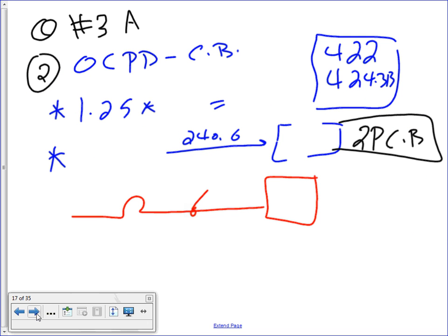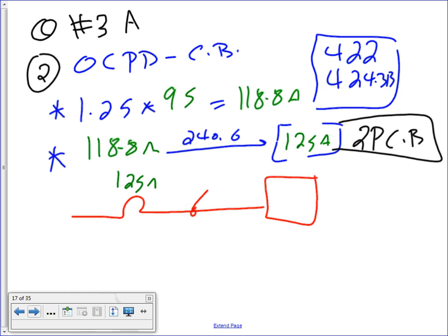Overcurrent protection device. We're assuming, guys, it's a continuous load. It's an appliance, but it's a heating appliance, so they allow you to use 95. So you take the 95 multiplied by 1.25. That will get you the same thing, 118.8 amps. Your reference is 422.11, 424.3(B), which tells you to multiply by 1.25. You take the 118.8 amps, 240.6, that will get you a 125 amp 2-pole circuit breaker. Then you put yourself a 125 amp circuit breaker and your number 3 MC cable to feed this one, which will be feeding the 95 amp.